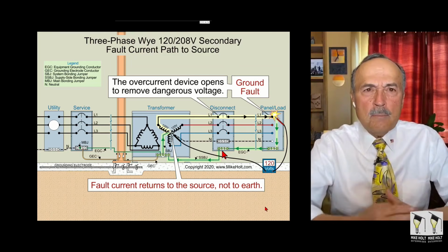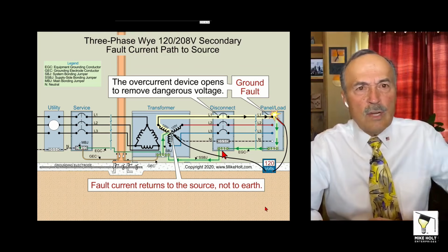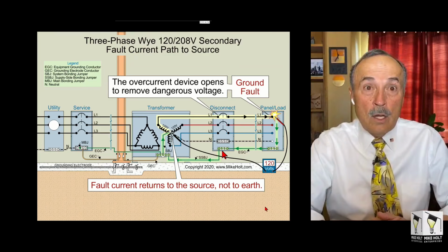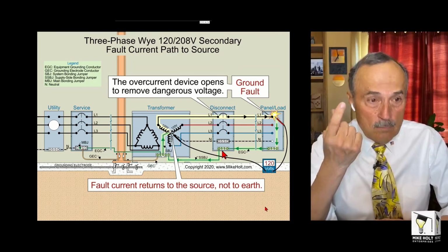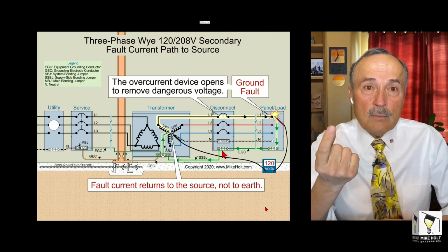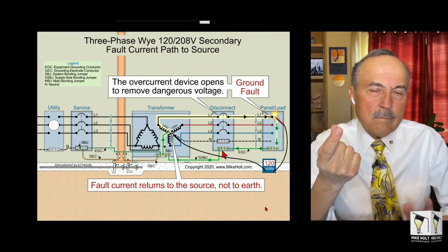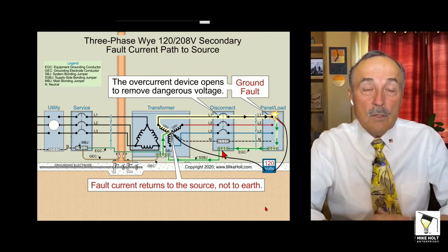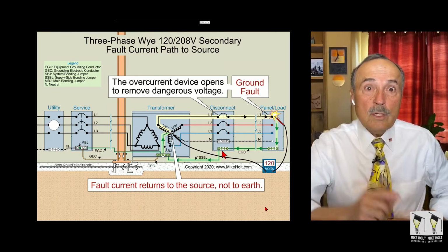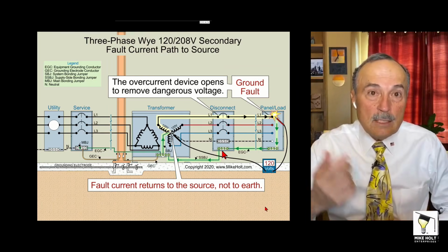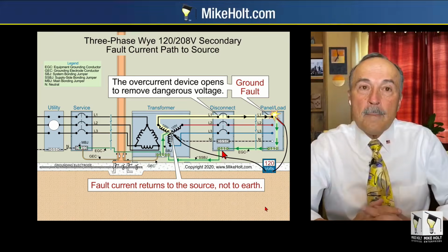I don't want to put the system bonding jumper and the grounding electrode at the transformer because I want to do it right here at the disconnect. Well, then you're going to get a disconnect that has what? A system bonding jumper. We call it a main bonding jumper, but that's for services, but it's going to be your system bonding. So yeah, you'd have to use one that you can do it, which they make. That's just the way they make them. You're going to get them that way. All right, we got one more here. If you have a metal conduit between the transformer and panel, does the ground conductor have to bond to the conduit?